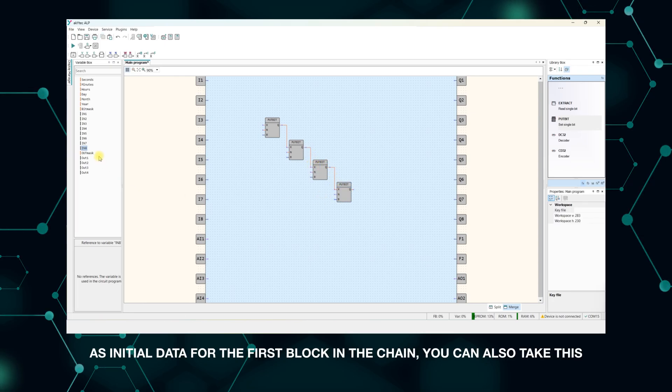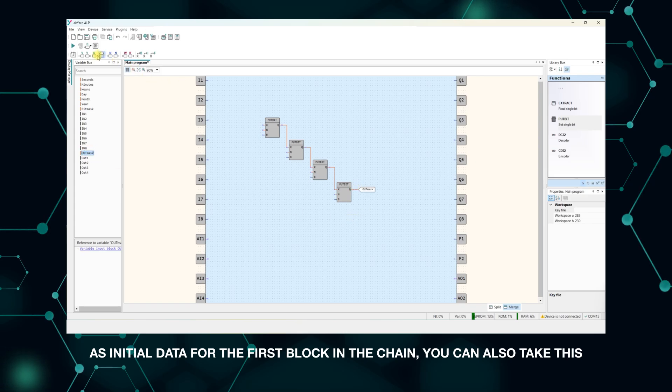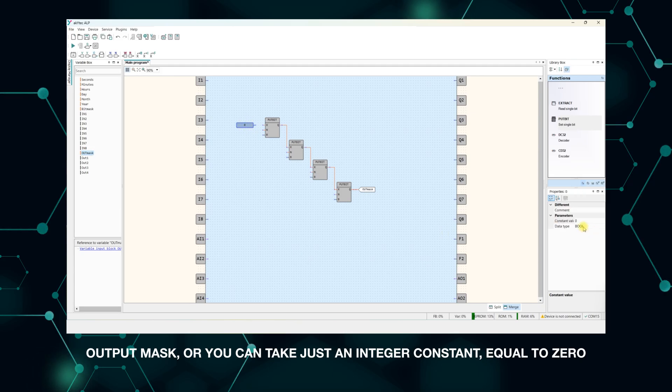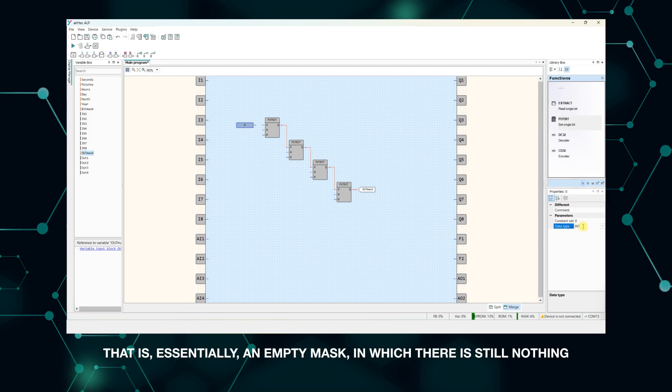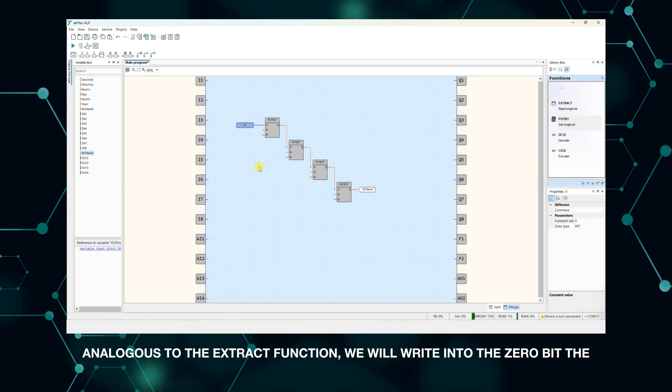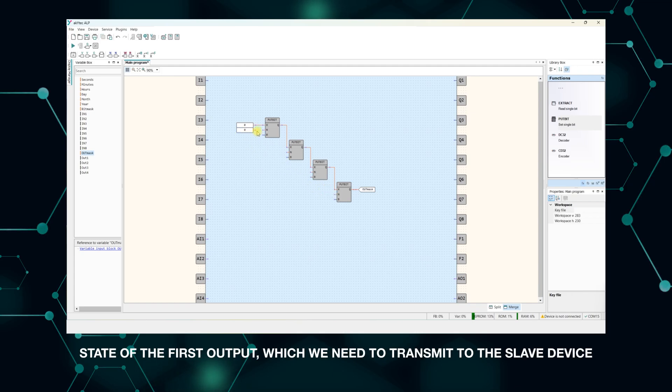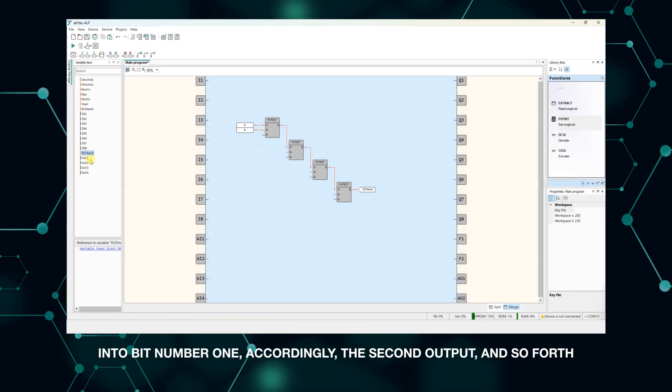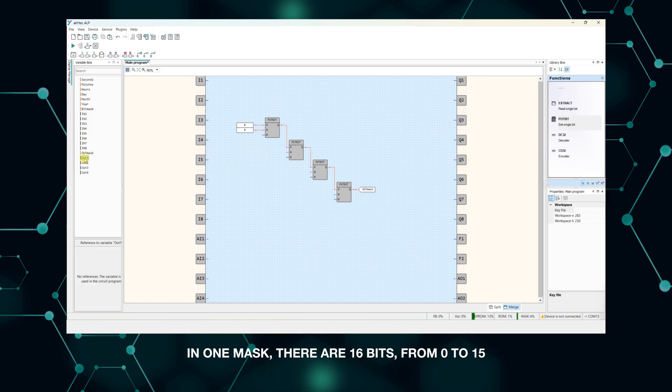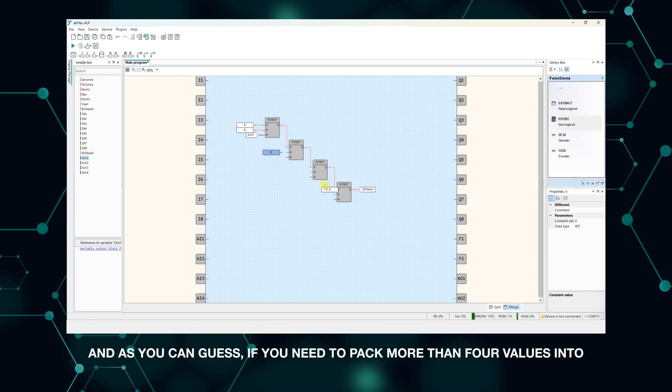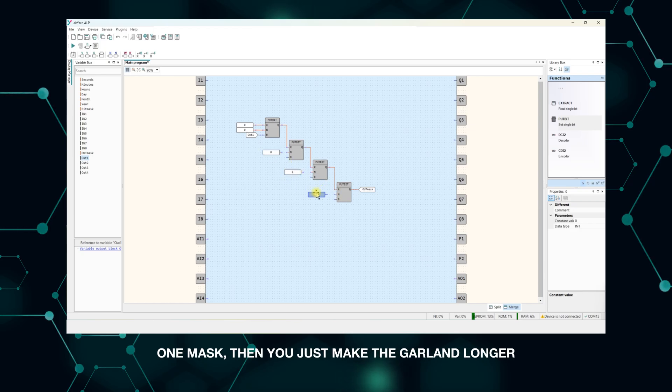As initial data for the first block in the chain, you can also take the output mask, or you can take just an integer constant equal to zero—that is, essentially an empty mask in which there is still nothing. Analogous to the extract function, we will write into the zero bit the state of the first output which we need to transmit to the slave device, into bit number one accordingly the second output, and so forth. In one mask there are 16 bits, from 0 to 15. And as you can guess, if you need to pack more than four values into one mask, then you just make the chain longer.